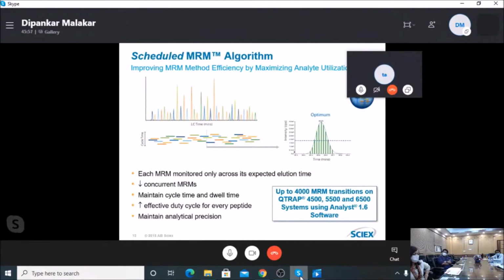So scheduled MRM is one of the things, because with 4000 transitions in one go in a normal MRM, we cannot get a good number of data points for each MRM transition. So we need to schedule it. That means we have to run a single MRM, different MRM experiments, different MRM transitions - maybe 300 or 400 MRM in one run. That way you can run it like 10, 12, or 15 times to accommodate all the MRMs, monitor the retention time for each of the MRM peaks, and then feed all this retention time into the final method. This is called scheduling of the MRM.